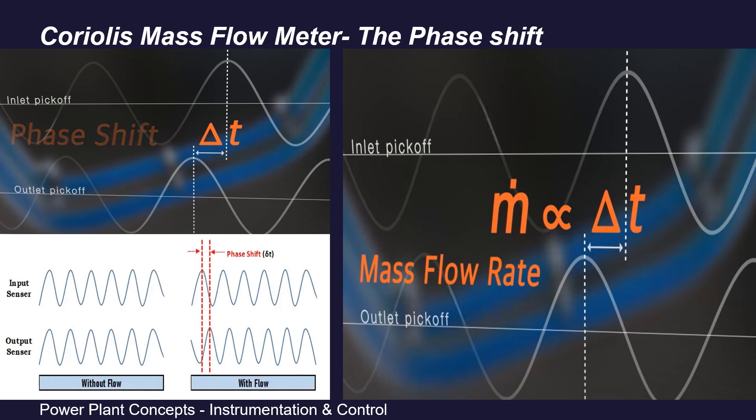The time delay measured between the two sine waves is in microseconds and is called delta T (ΔT). This delta T is directly proportional to the mass flow rate. The greater the delta T created by the Coriolis forces, the greater is the mass flow rate.